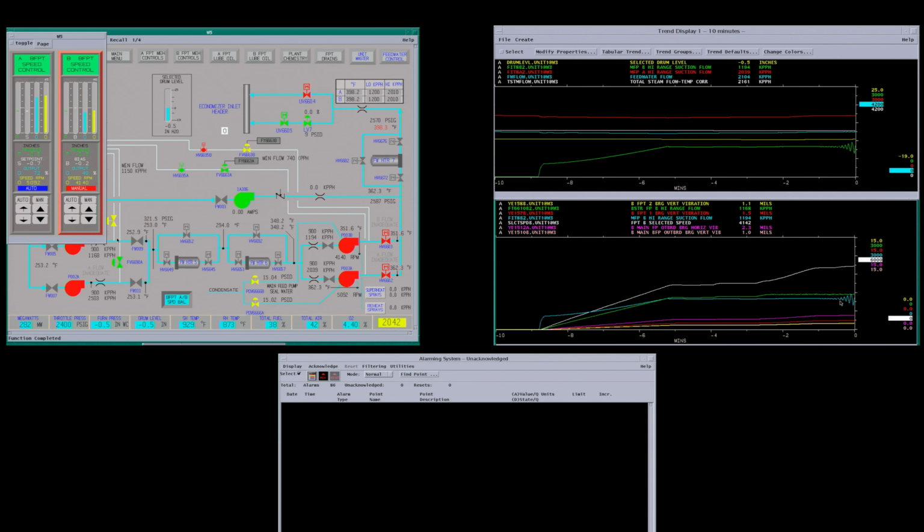Okay, this is what you want to avoid right here. We're showing cavitation on the main feed pump. It's creating a lot of force on the pump and the turbine shafting, not to mention the water piping and your feed water heater. It goes from here to feed water heater 7, then it goes up to the economizer in the boiler.